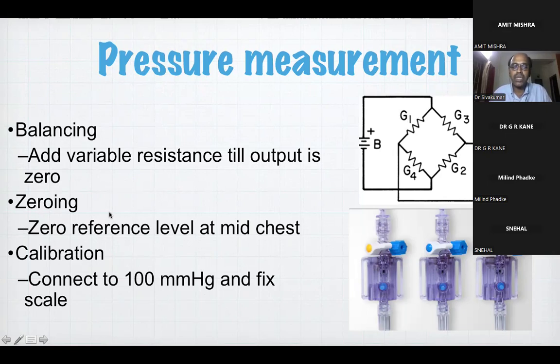So balancing is the process through which the machine gives an output of 0 without any connection of the transducer. What is zeroing? So very often we will say zero the transducer, and what we mean by zeroing the transducer is actually balancing the transducer. Zeroing is something different. Zeroing is moving the transducer level. So this is the 0 level of the transducer. This 0 level of the transducer is moved to the mid-chest level. So moving it up or down to the mid-chest level is called zeroing the transducer. When we say in the cath lab to the technician, zero the transducer, what he does is balancing the transducer. And zeroing the transducer means pushing the transducer either up or down in relation to the mid-chest.